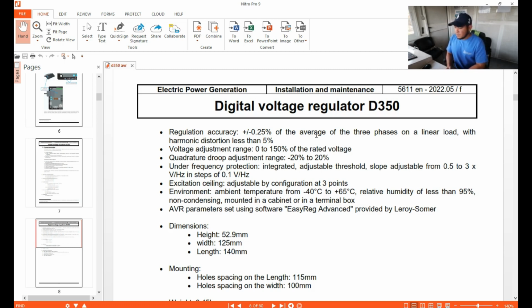For the environment, the ambient temperature, which is what we call the working temperature of this AVR, can range from negative 40 to 65 degrees Celsius. The relative humidity is less than 95%.